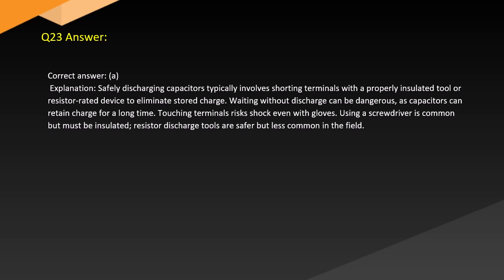Answer. Correct answer: A. Explanation. Safely discharging capacitors typically involves shorting terminals with a properly insulated tool or resistor-rated device to eliminate stored charge. Waiting without discharge can be dangerous as capacitors can retain charge for a long time. Touching terminals risks shock even with gloves. Using a screwdriver is common but must be insulated. Resistor discharge tools are safer but less common in the field.